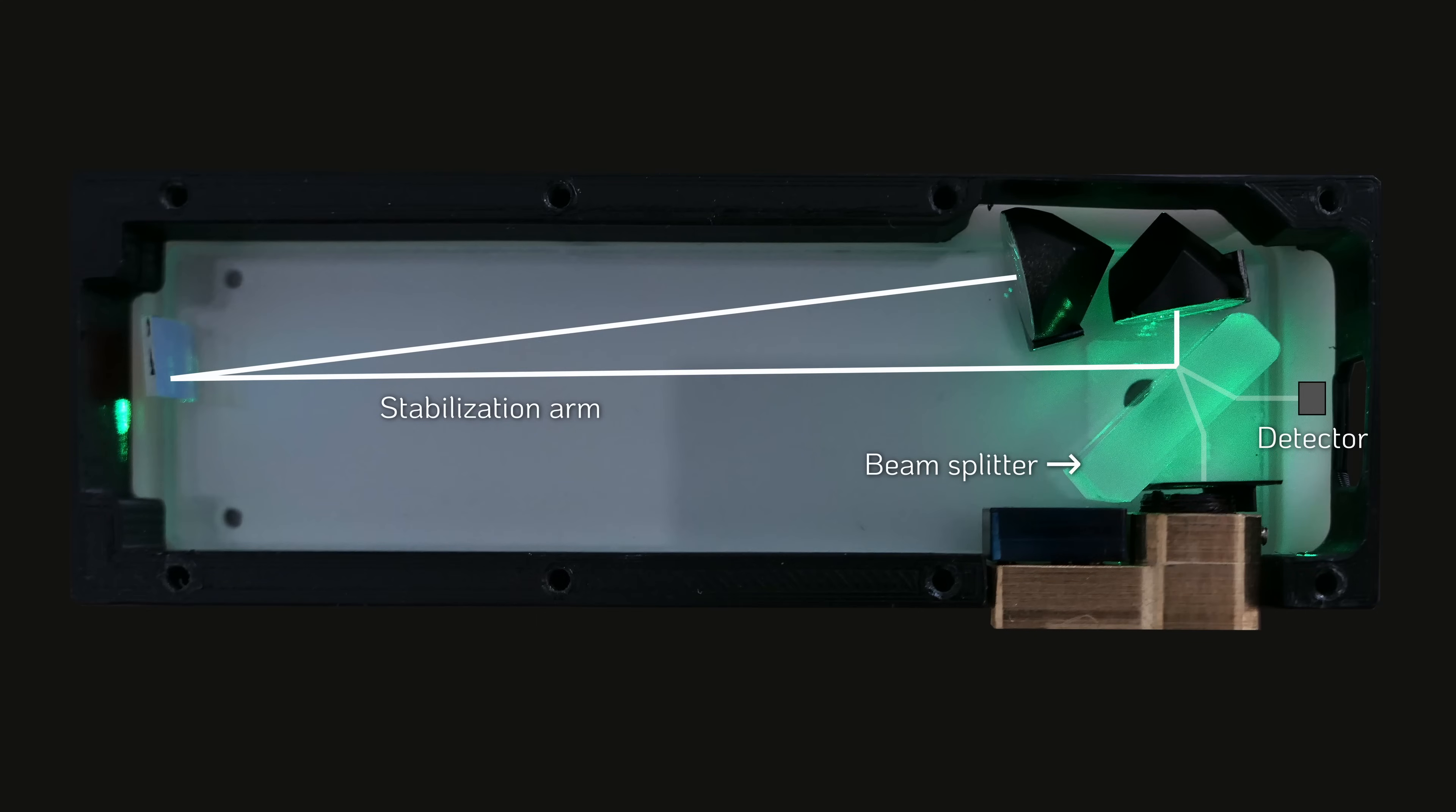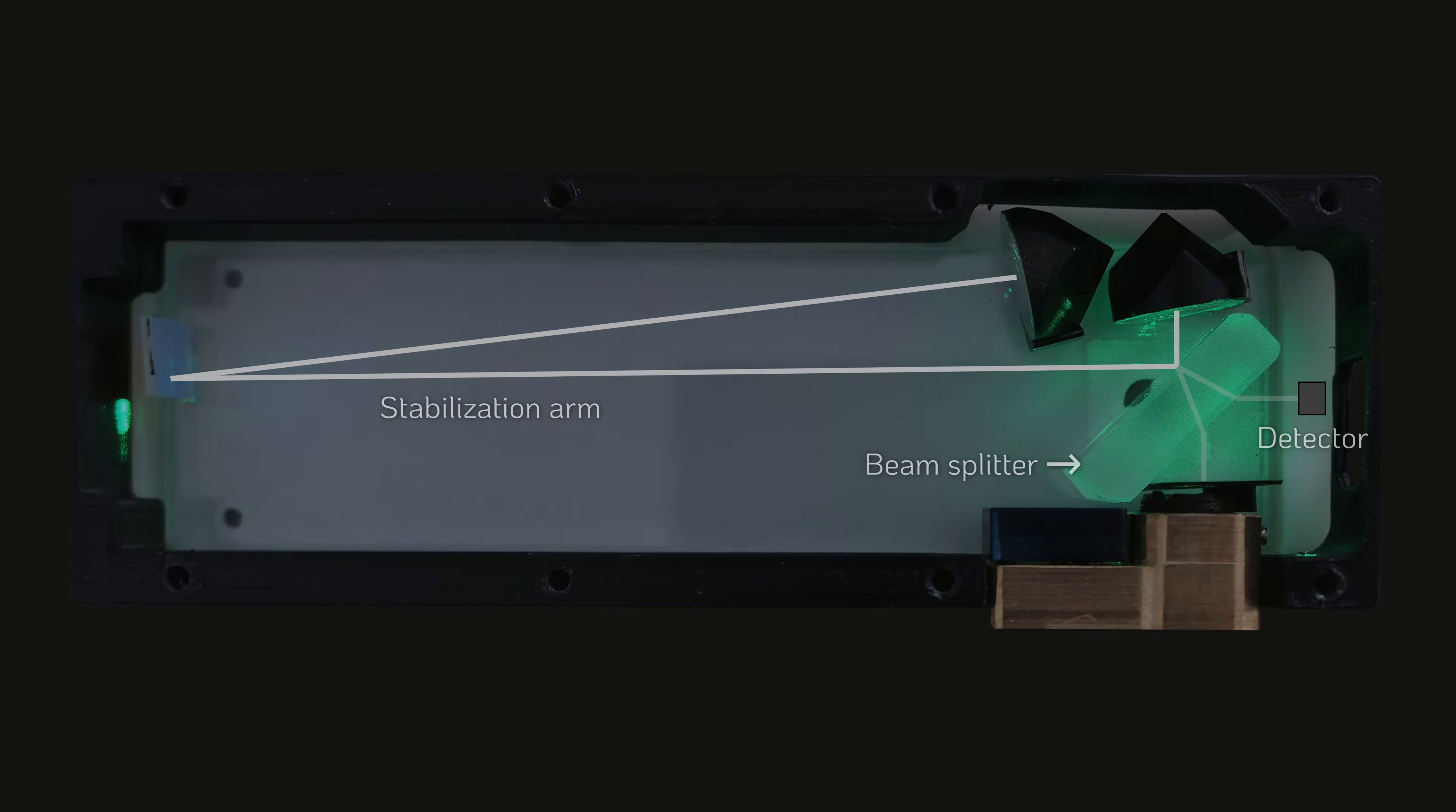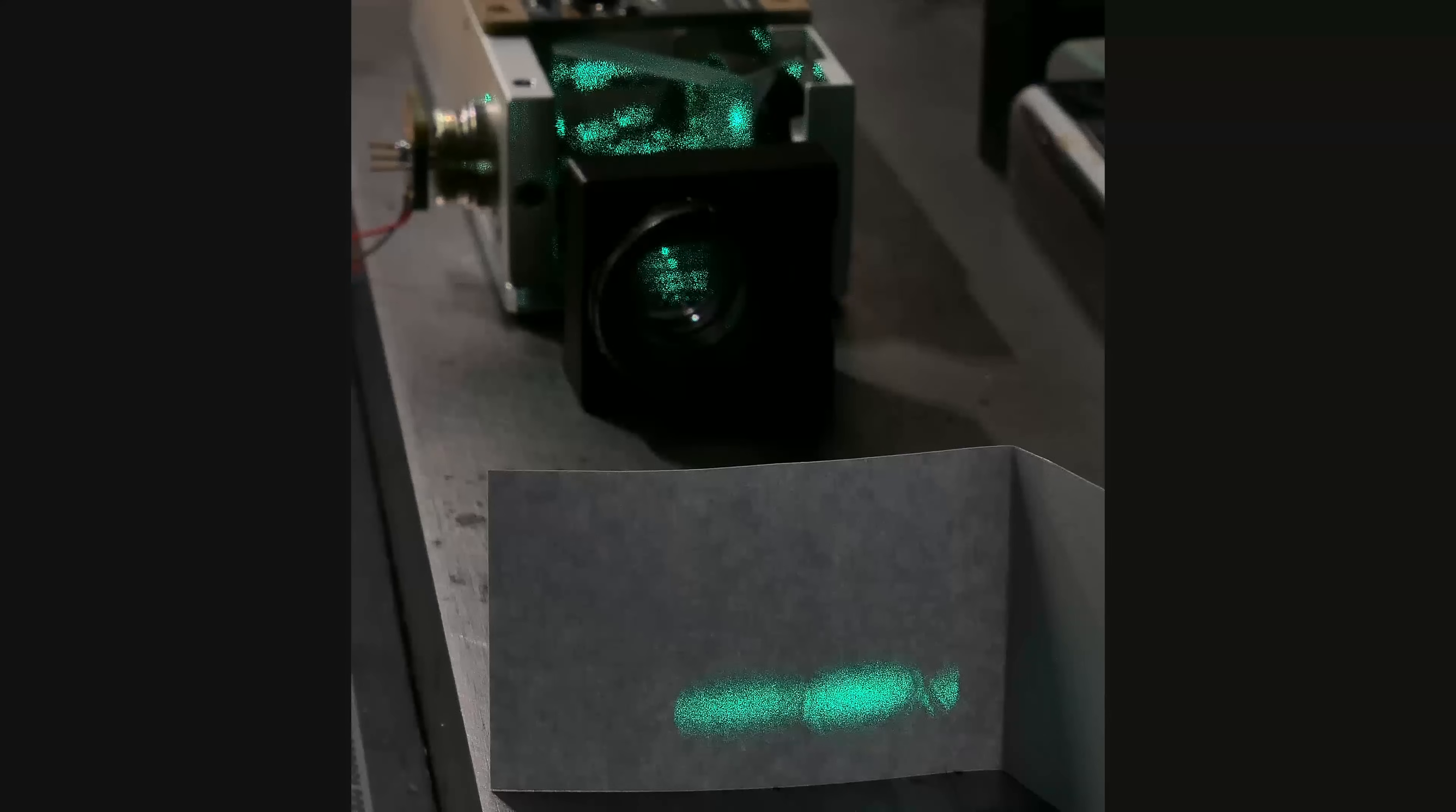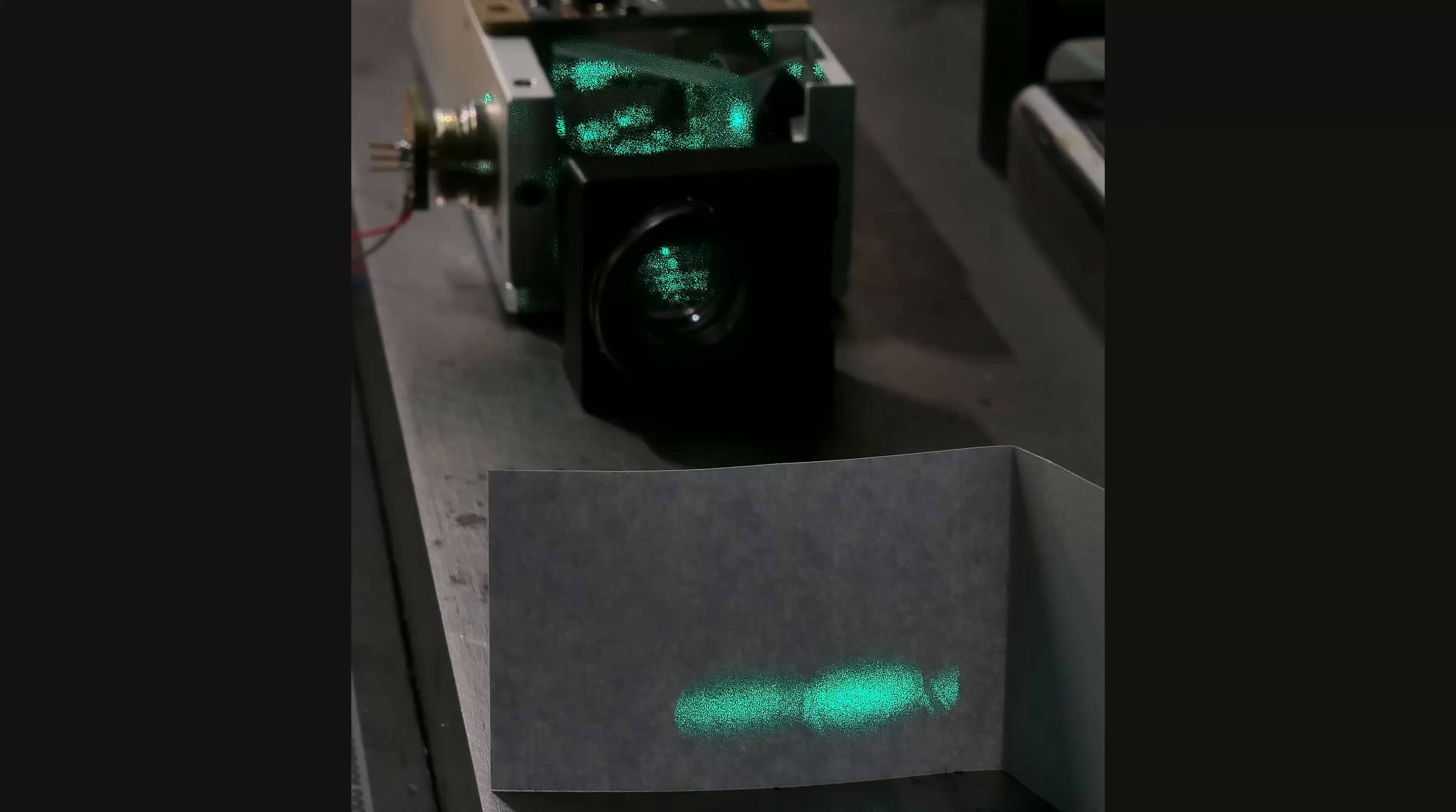To solve this problem, the design uses both sides of a glass plate as a dual beam splitter, effectively creating two interferometers simultaneously. In the stabilization arm, the light travels a fixed distance before being measured by a detector. The resulting interference signal makes it possible to detect any changes in the laser's wavelength. A microcontroller then changes the drive current and temperature to compensate for any wavelength drift of the laser diode.